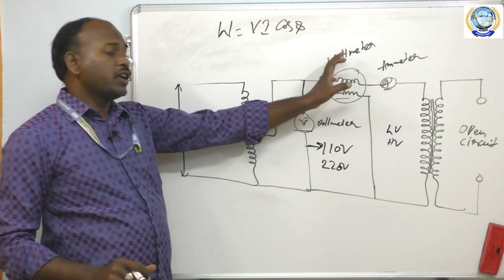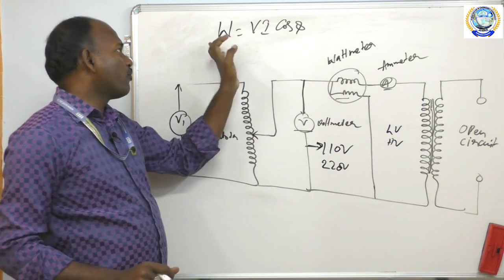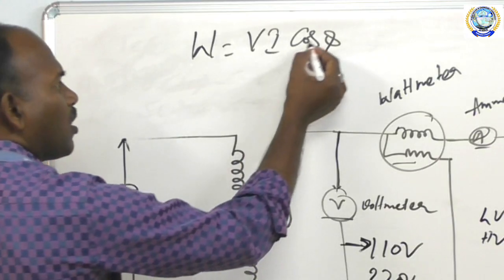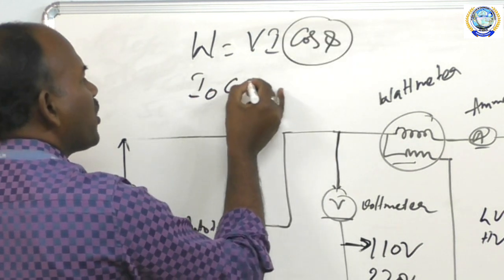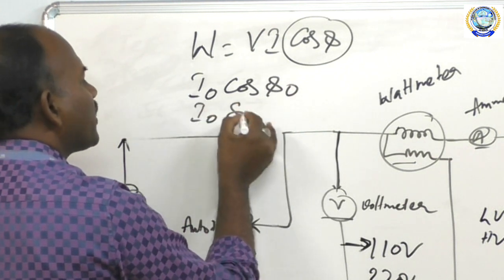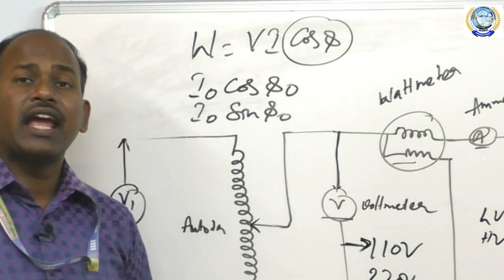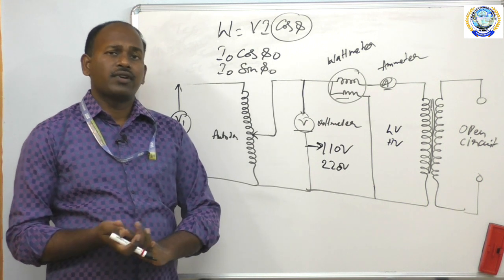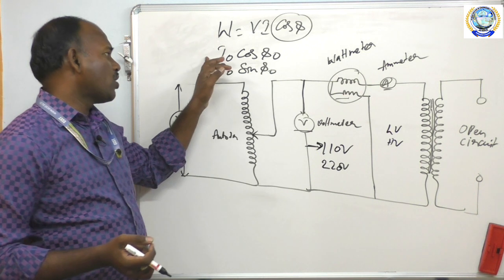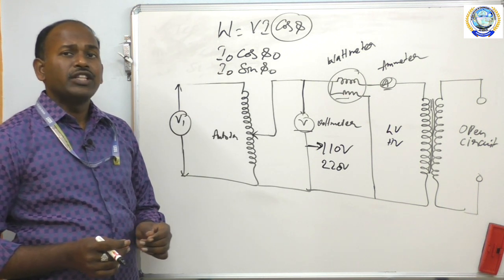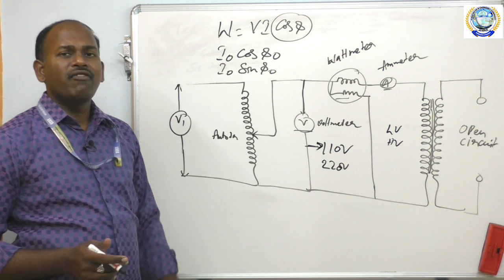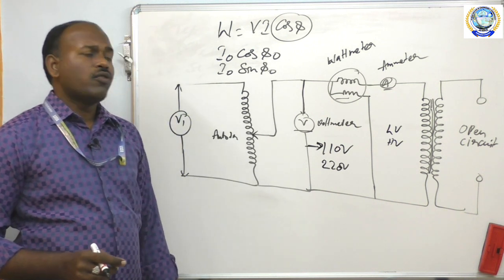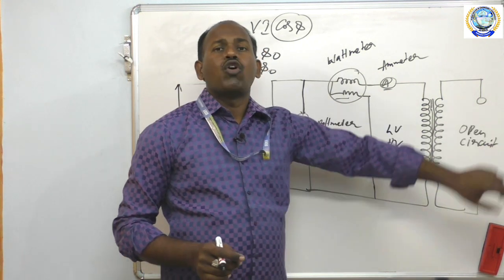From the wattmeter, voltmeter, and ammeter readings you calculate cos φ. Once you know cos φ, you calculate I0 cos φ0 (working component of current) and I0 sin φ0 (magnetizing component of current) — as previously discussed in the transformer no-load phasor diagram. By observing these two values you calculate the required loss values. In the open circuit test you obtain iron losses along with a small amount of copper losses, since the secondary side is open-circuited.